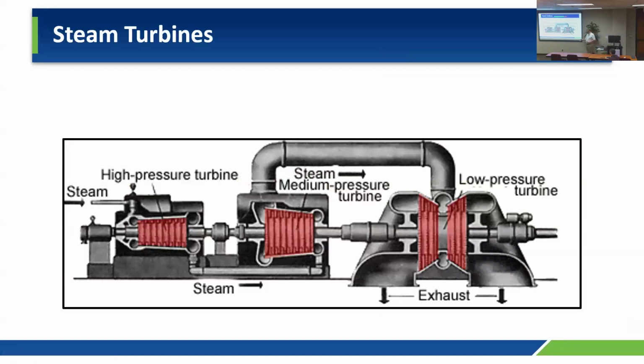Steam turbines are a little different. For gas turbines, we bring in natural gas and combust it to generate electricity. But what if you already had access to steam? If you've got high pressure steam, you send it through a high pressure turbine and extract some of its energy, leaving medium pressure steam that goes through a second turbine. After extracting more energy, you've got low pressure steam that goes into a low pressure turbine, producing exhaust. If you're smart, you put them all on the same shaft so they're all contributing work to the generator.